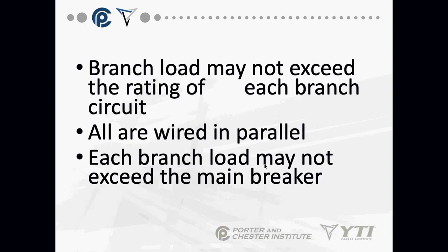Okay. Again, branch loads may not exceed the main load. Neutral comes from the center tap of the transformer. Ground should be connected to the grounding rod, not to a water pipe. Remember what I said, water pipes change over time. Very often in older construction, you will see ground connected to a water pipe in the basement. You can follow the ground wire out of the box and it's connected to a copper water pipe. That's not a good idea. Okay? Doesn't work too well.